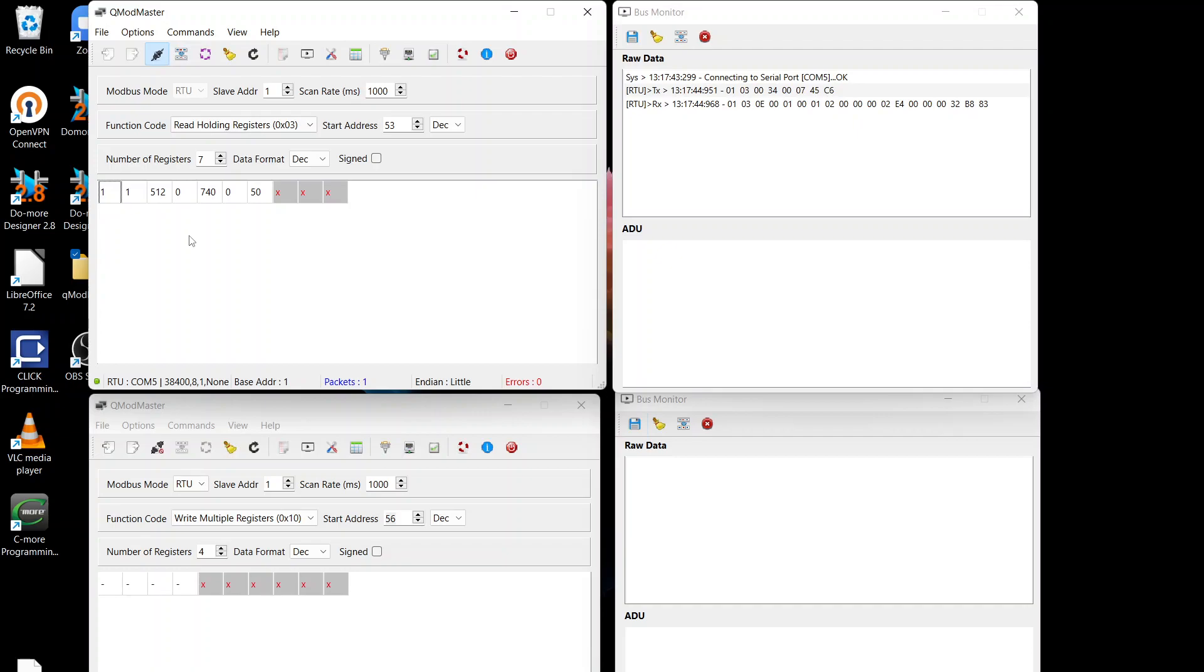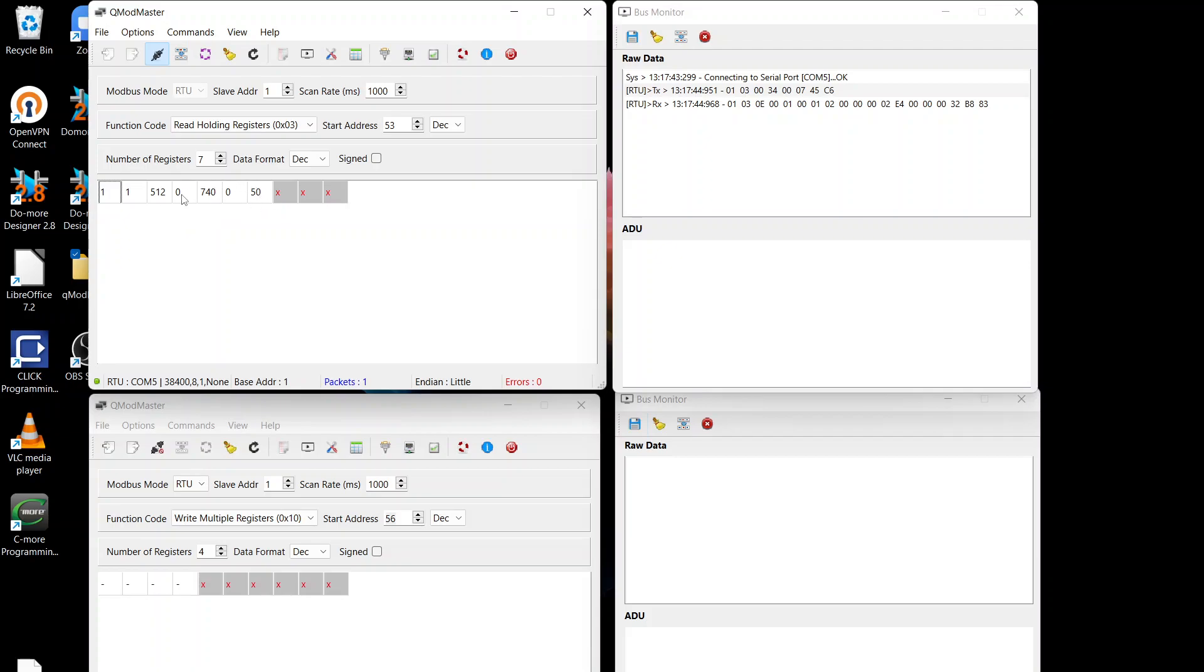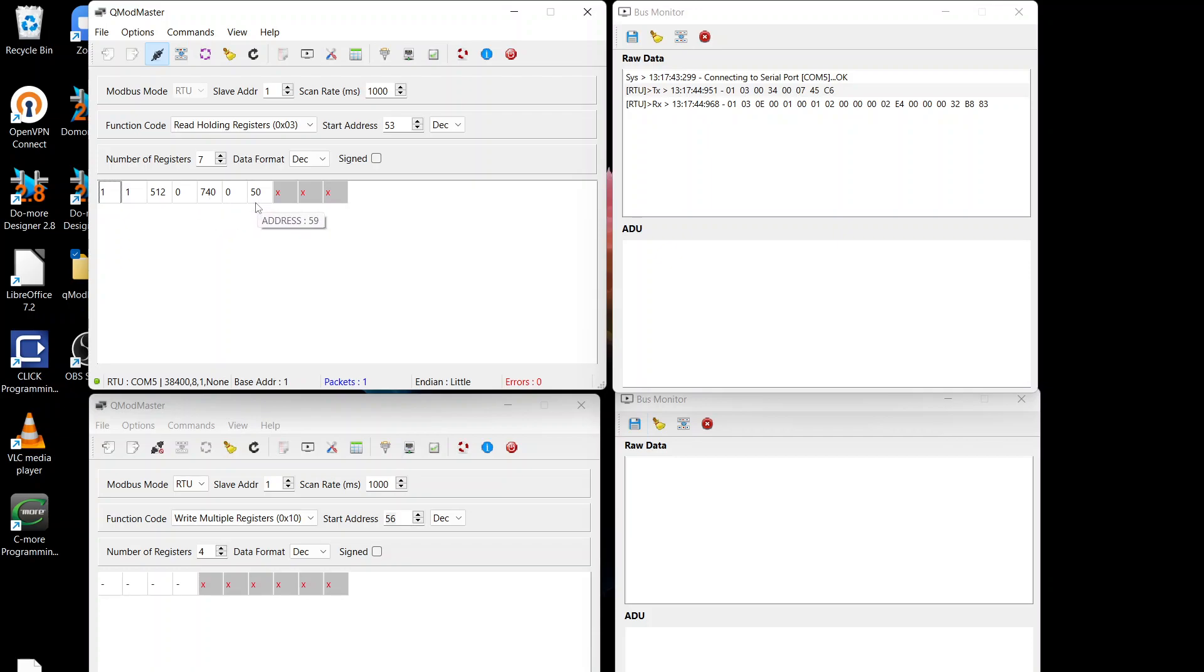We can see currently we've got the first set point enabled. This is the channel number, so it's channel 1. This is the status mask to let you know whether there's no flow or if there's any other errors. And then these four registers here are the ones that we're interested in. They're the actual set values. So it's currently set at 7.4 with an offset of 0.5.